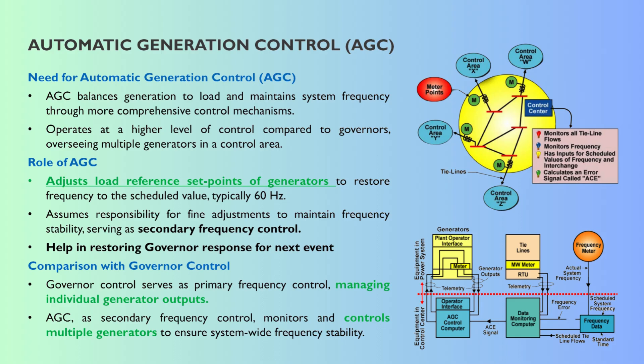That really clarifies the whole picture — it's a layered defense. You've got inertia as the instantaneous physical buffer, then the fast proportional primary control from governors using droop for stability, and finally the slower, precise secondary control from AGC to restore the exact frequency target and manage overall balance. A really elegant hierarchical system built up over decades. The most surprising thing is that droop characteristic — intentionally designing the primary control to be imperfect is actually the key to making the whole interconnected system stable. Sometimes perfect individual action isn't as good as coordinated proportional cooperation, especially in complex systems.